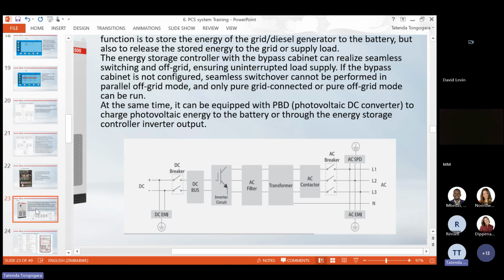So the challenge we are having is that you have inductive loads running on your system. You see your total peak load is 400 kilowatt, and then you put a PCS 500. Your system is running at 350 kilowatt, then you start a 50 kilowatt motor, and your startup currents will cause the system to go into an overcurrent fault, because starting a direct online motor can go as high as 5 to 7 times the normal operating current.